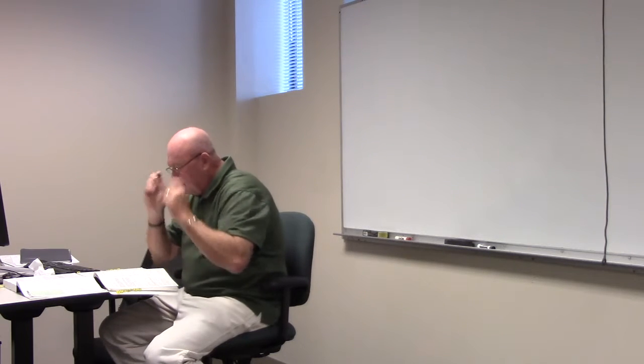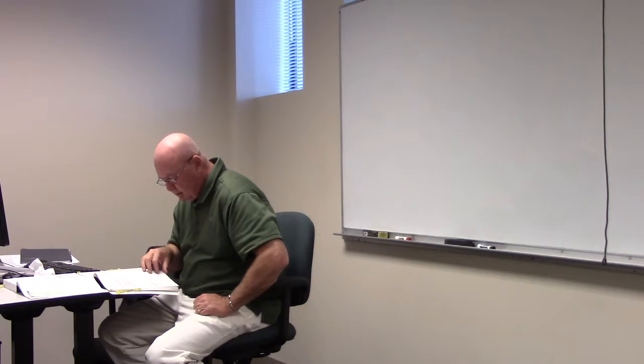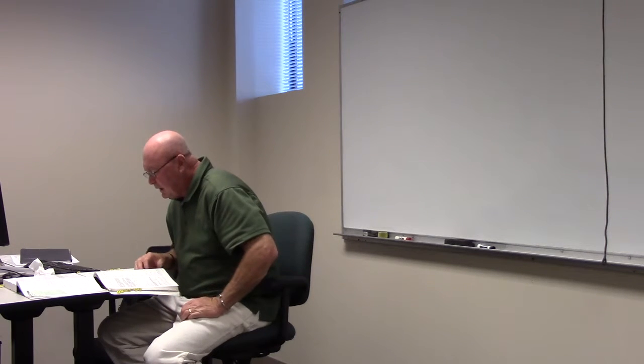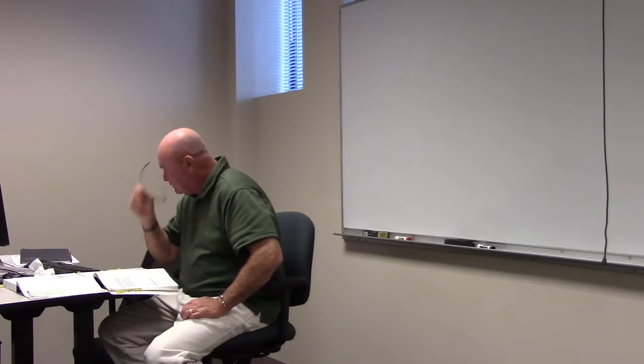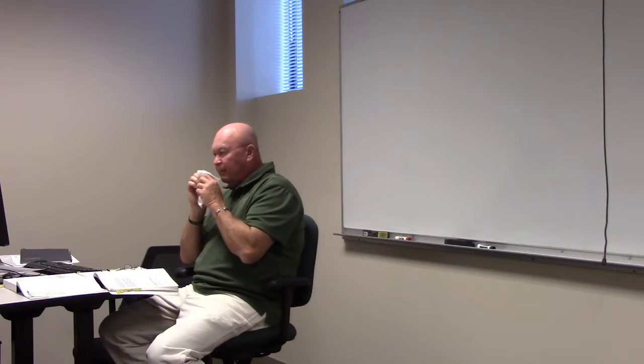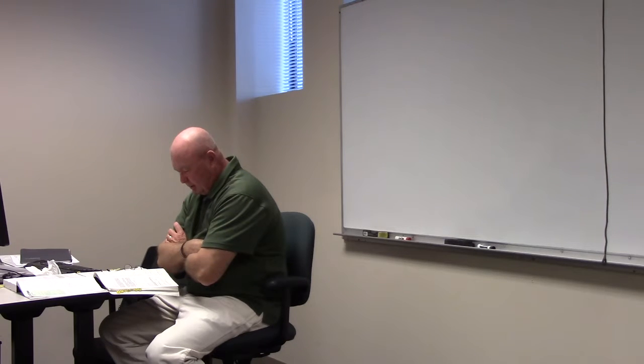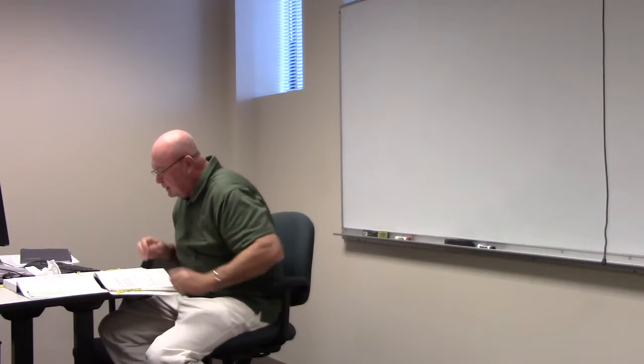Makes sense, doesn't it? The next bullet point there is 220.14D, luminaire. It says an outlet supplying a luminaire shall be calculated based on the maximum volt-amps of the equipment and lamps. In other words, we look at whatever the wattage of the lamp was to determine that load. 220.14F, we went over that. That's talking about signs. How many volt-amps is a sign? 1200, yeah. How many volt-amps is just a regular receptacle? 180. How many volt-amps is a show window per foot? 220.14G. 200. Okay. All right.